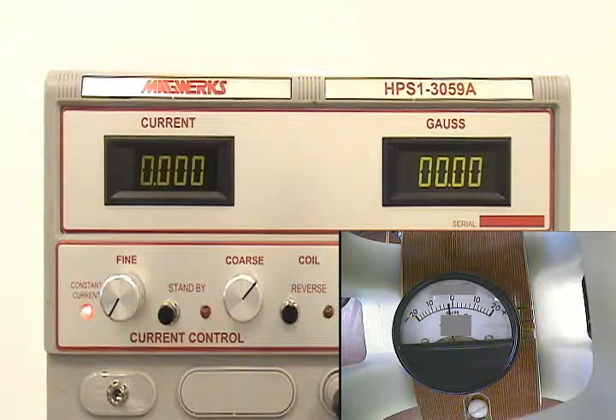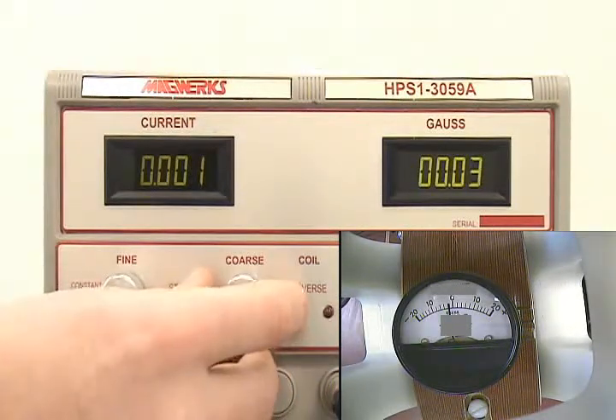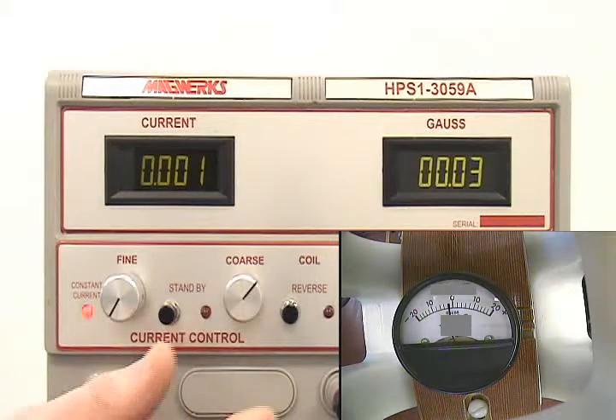Again, we see the magnetometer appears to be off about two times. To figure out exactly how much error the magnetometer has, we will switch to manual mode, adjusting the output power which changes the magnetic field in the coil.